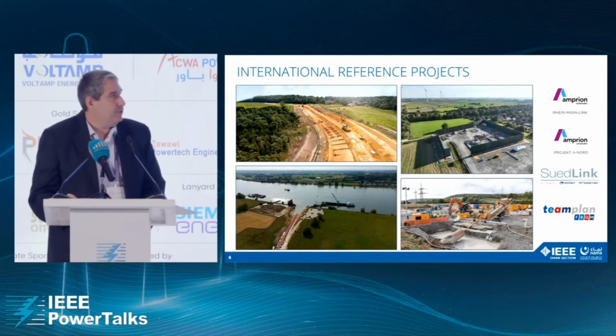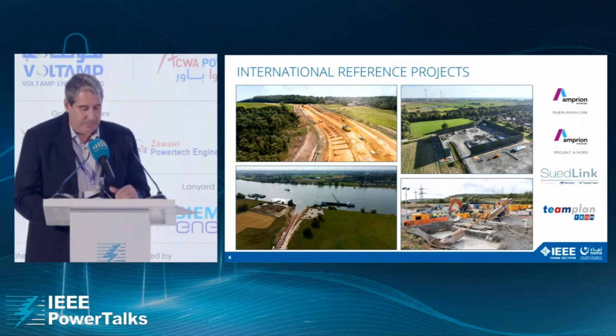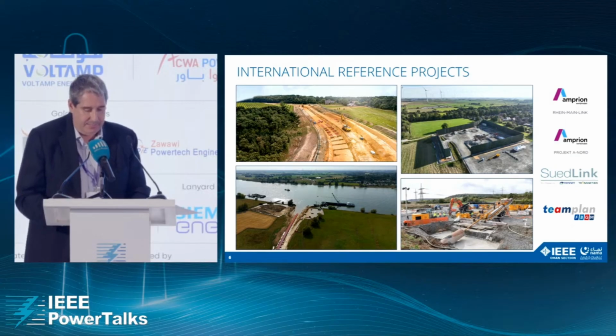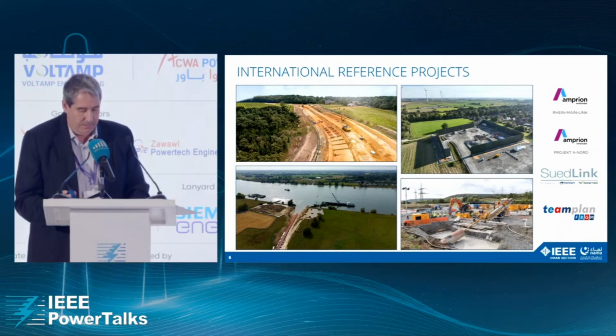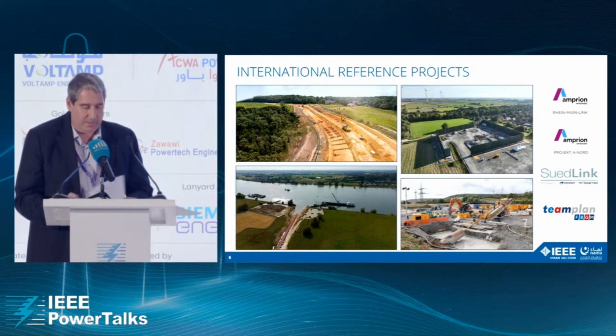As the illustration on the slide shows, the open construction method is not the optimal solution in this case. In particular, when crossing bodies of water or roads with underground cables, the closed construction method, despite higher costs and longer construction times, offers a clear advantage in terms of space for the construction. Set-up is only required at the start and end point of the route. Various methods are available for implementation, including pilot tube jacking, horizontal directional drilling, and microtunneling. The choice of the appropriate method largely depends on local geology and the length of the route to be installed.